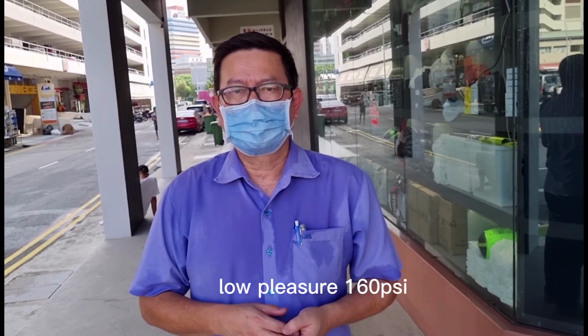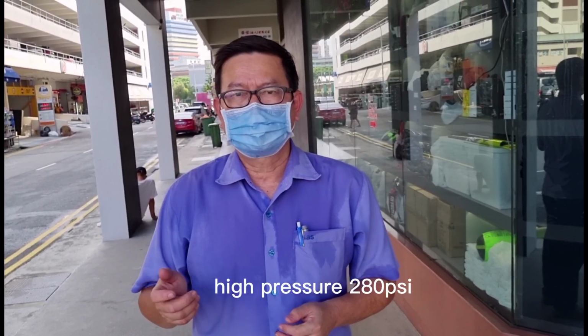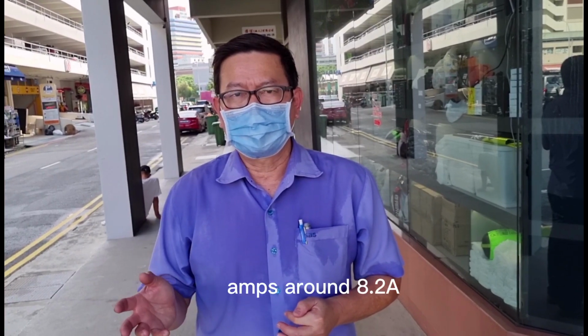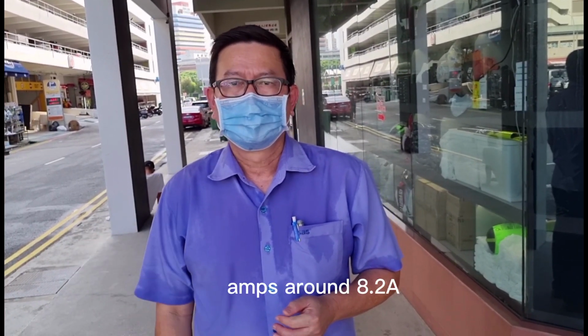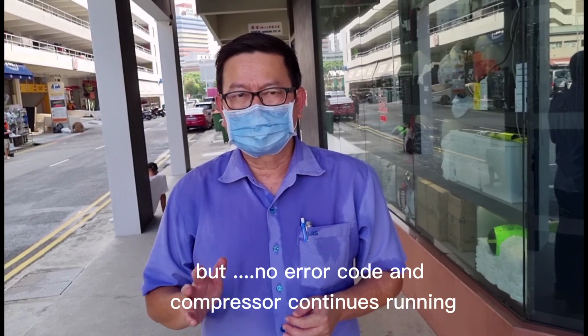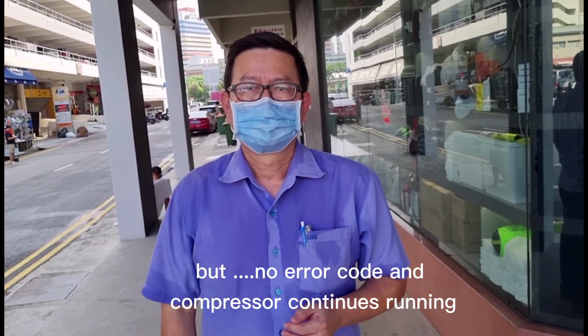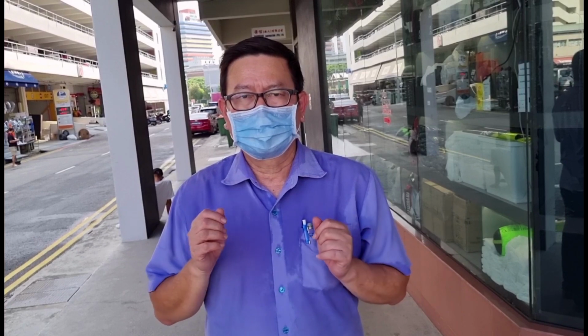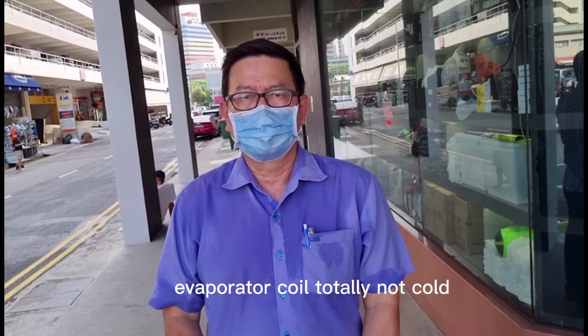Low pressure is around 160, high pressure 280. Ampere is around 8.2 amp, but no error code. Compressor continuously running, no error code, but the evaporator coil is totally not cold.